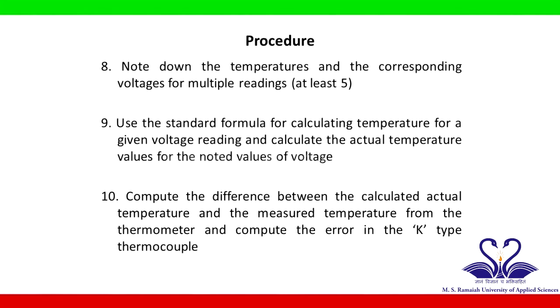Tabulate the temperature voltage combination readings for at least 5 values. Use the standard formula for calculating the actual temperature values for the obtained voltage readings for a K-type thermocouple. Find the difference between the calculated actual temperature and the measured temperature obtained from the thermometer to obtain the percentage of error in the K-type thermocouple.